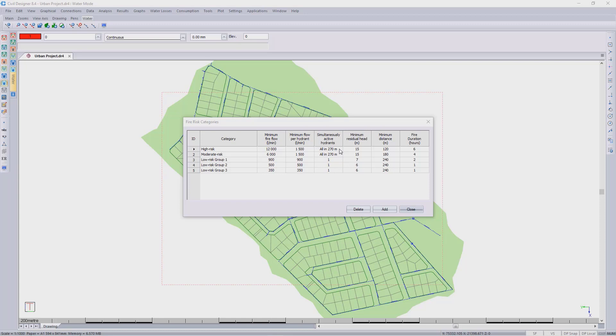This is to calculate the flow requirement for all of these hydrants to be switched on. The required residual head at each hydrant for the high risk will be 15 meters. The placement of each hydrant will be 120 meters apart, and the fire flow duration will be six hours for the high risk. Each category will have different values.